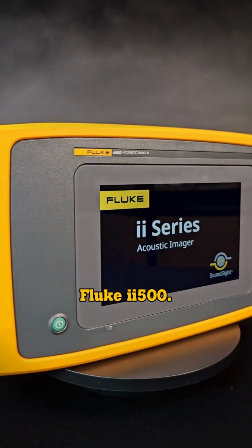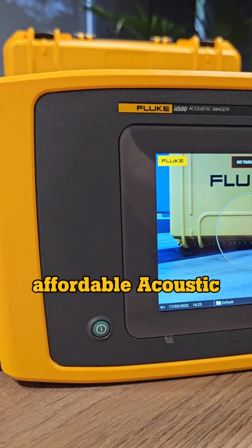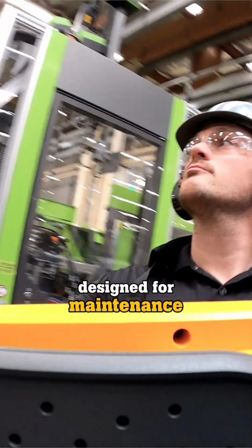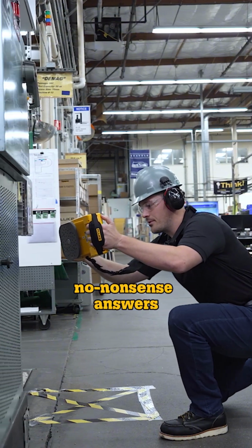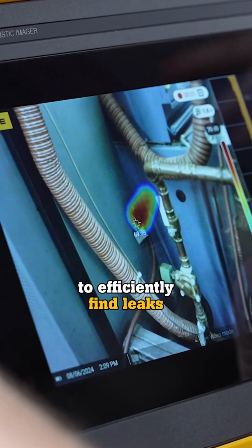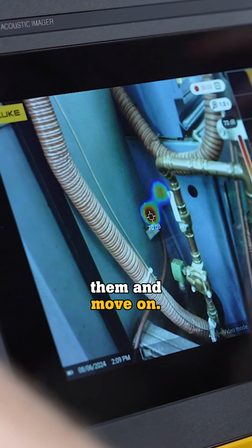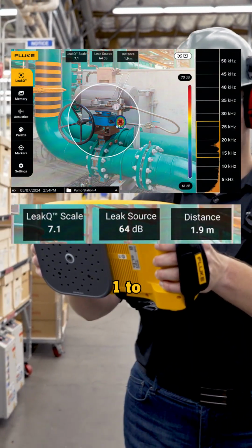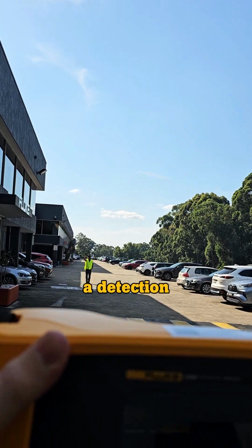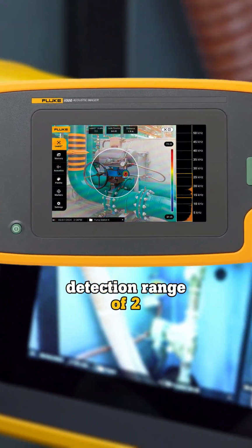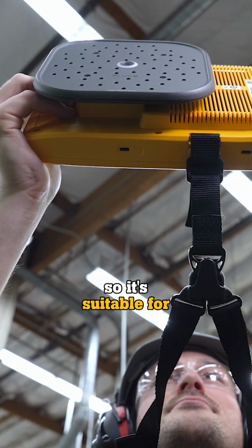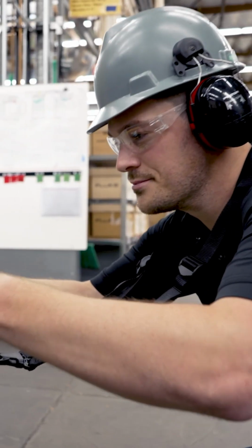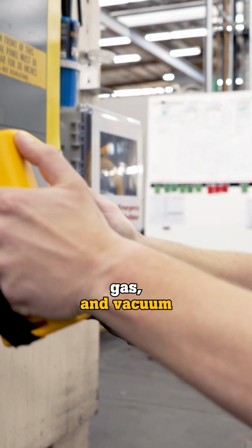Let's start with the Fluke ii500. This is Fluke's most affordable acoustic imager, designed for maintenance technicians who need quick, no-nonsense answers to efficiently find leaks so they can fix them and move on. It offers an easy-to-understand 1 to 10 leak severity scale, a detection distance of up to 50 meters, and a frequency detection range of 2 to 52 kHz, so it's suitable for detecting all sorts of pesky hidden compressed air, gas, and vacuum leaks.